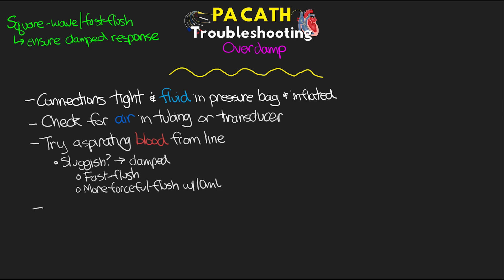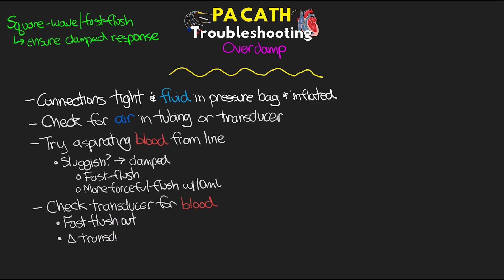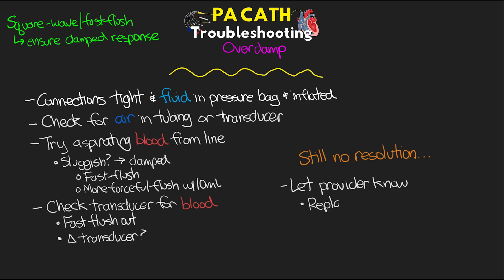Check the transducer and make sure there's no blood in there. If blood is present, try fast flushing it out. If it's still damped after that, try replacing the transducer. If we still have no resolution, let the provider know, as the catheter may need to be replaced.